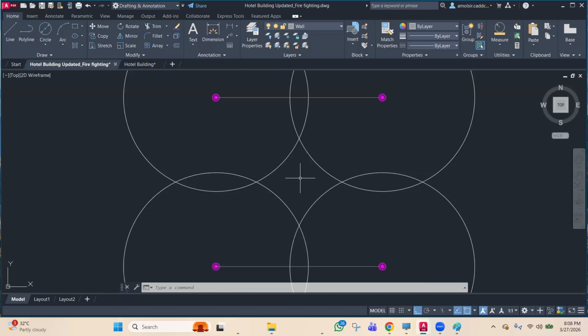Okay. So better is what? Always do not maintain the maximum distance. If you are maintaining this maximum distance, maximum you can go up to 4.5 meter, but you can see the dead zones are creating. So there is a minimum distance provision also, like we are having minimum 7.5 feet, maximum 15 feet. So between 7.5 to 15 feet you have to take. You should not always take 15 feet over here.